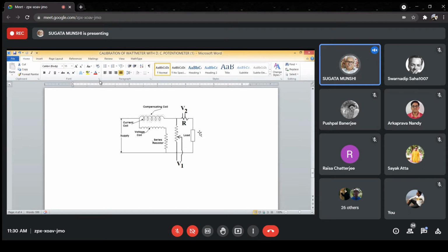Then you again change the load current so that the wattmeter reads 40 watt. When it reads 40 watt, what will be the load current? Around 0.4 ampere. So 0.4 ampere is flowing here. I am not using any ammeter. Again, I measure the voltage V1 to get the voltage across the load, and voltage V2, divided by R, will give you this new current close to 0.4 ampere. So when you get the accurately measured value of this current and this voltage across the load, then you get a wattage value. So instead of 40 watt, it may come out as 40.3 watt or 39.2 watts, like that.